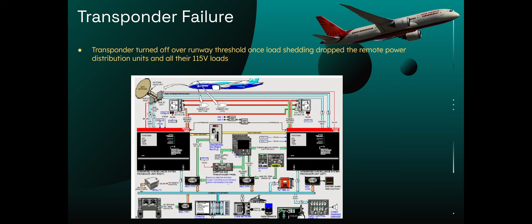Notice here, in the left captain instrument bus, there is a tie contactor called the captain's instrument tie contactor. It is normally closed. On the right is the right bus power control unit, the first officer instrument bus, and its bus tie contactor, normally open. So how does this work? When the bus power control unit is on and powered, it is holding that open with power, keeping these isolated. When this one is on, it's keeping that closed.